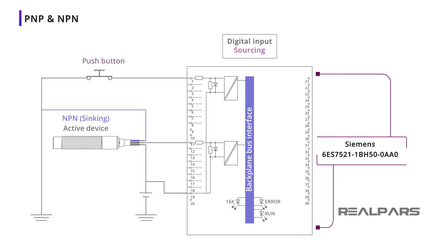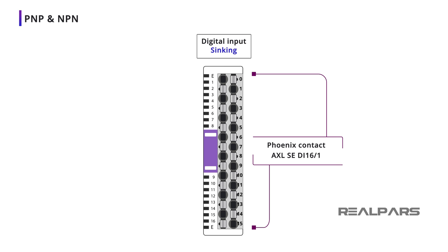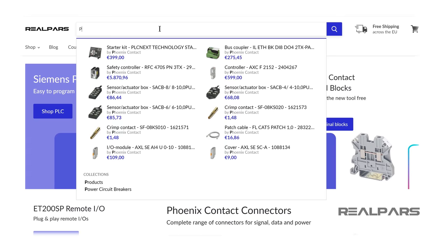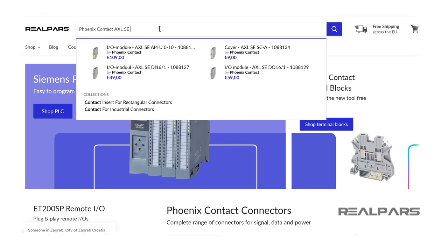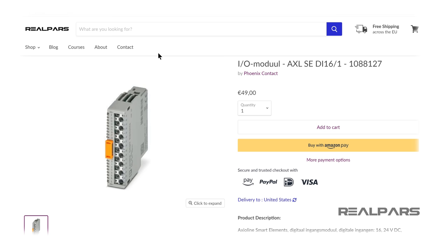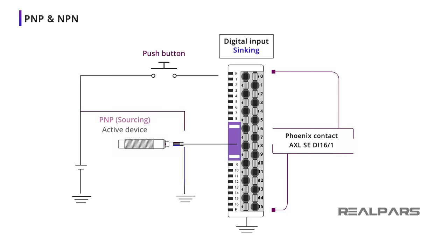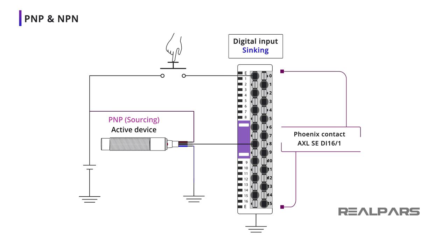Let's have a look at a sinking module. The Phoenix Contact Digital Input Module AXL SE DI16/1 is a sinking type. You can find the link to order this PLC module in the video description as well. Let's connect a push-button switch and a sourcing proximity sensor to two of the inputs. The current is flowing into the PLC module because it is a sinking type.